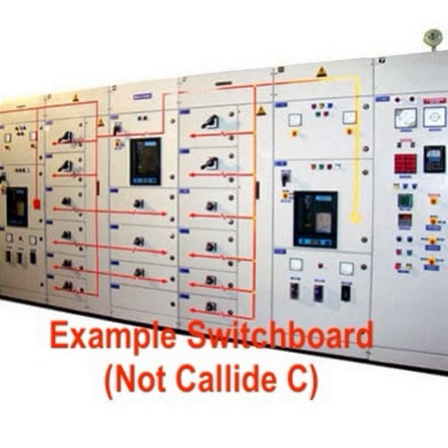The Callide substation breaker was configured to permit some reverse power flow, since during a plant startup, power flows from the grid into the unit switchboards to provide startup power to the required subsystems. Once the generator is up and running, it syncs to the grid and power flows into the grid, and we're up and running. The GCB, on the other hand, should never have any significant reverse power flow.